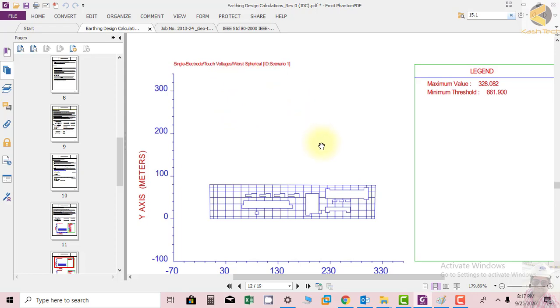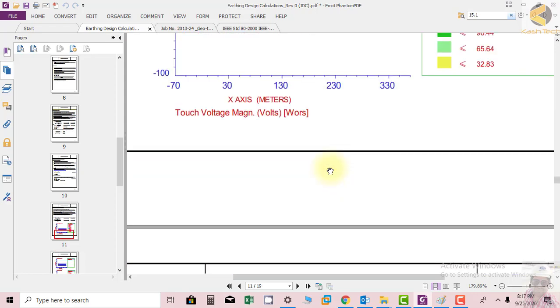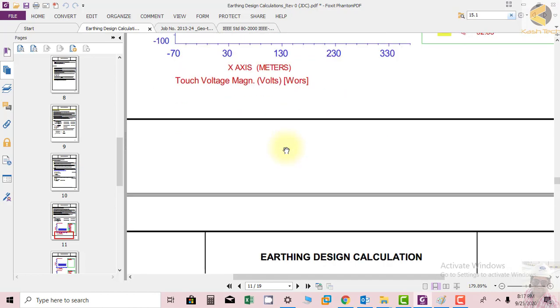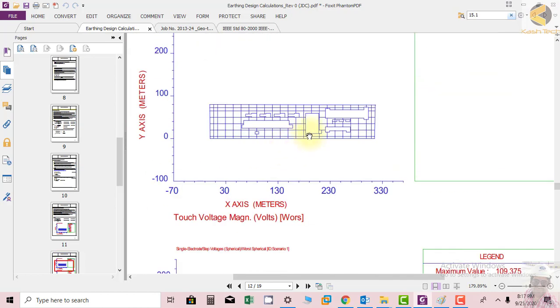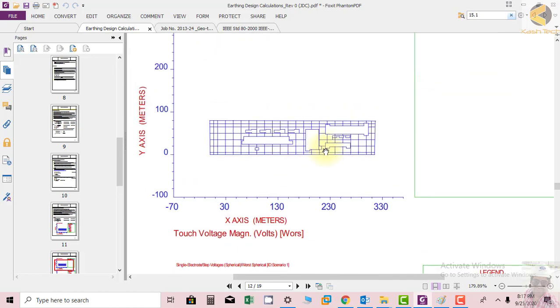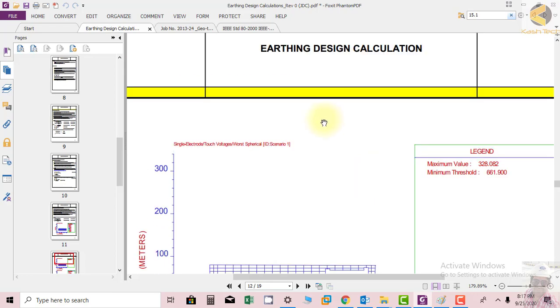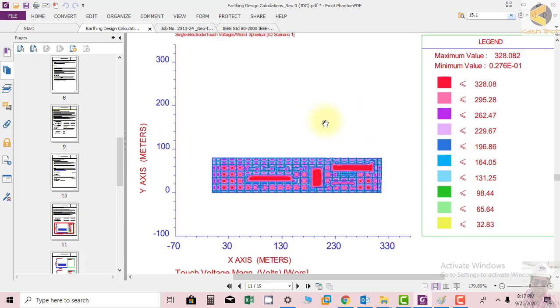In the previous section we have seen this red color which has the highest touch voltages, and these are shown in a spherical form. The minimum allowable is 661 and we are getting maximum at our substation is 328. This is basically another way of presentation.